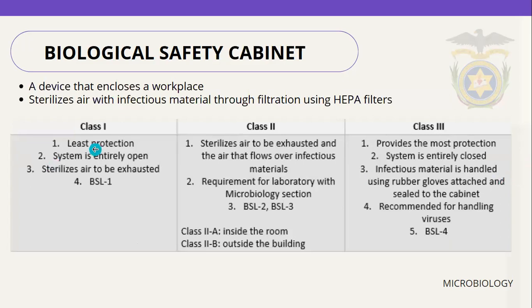Now let's proceed to the biological safety cabinet, and this is a device that encloses a workplace. It sterilizes air with infectious material through filtration using HEPA filters. HEPA means high efficiency particulate air, and the cabinets are classified according to the degree of containment they can afford.